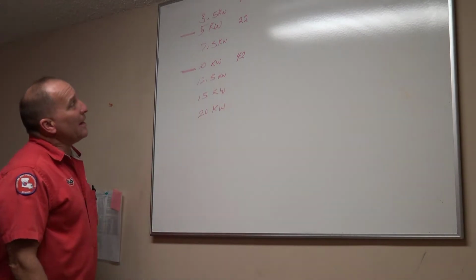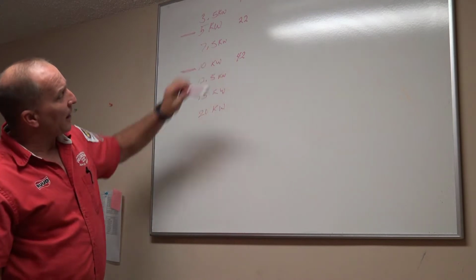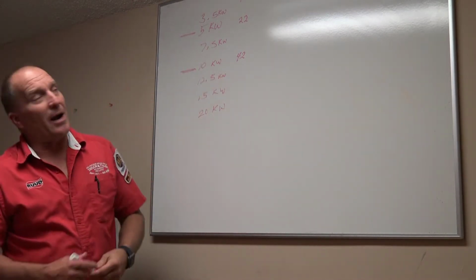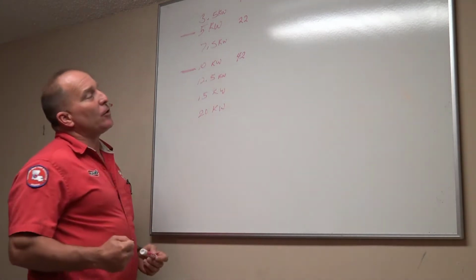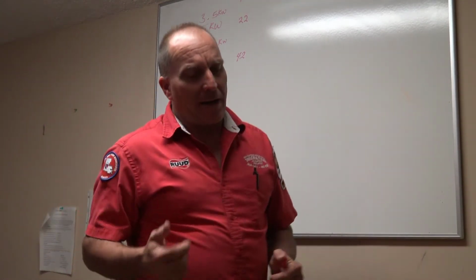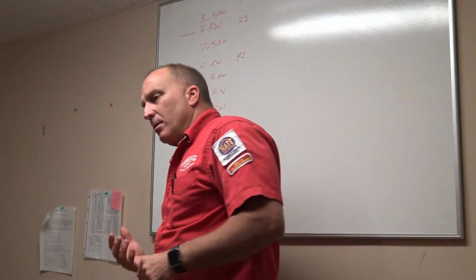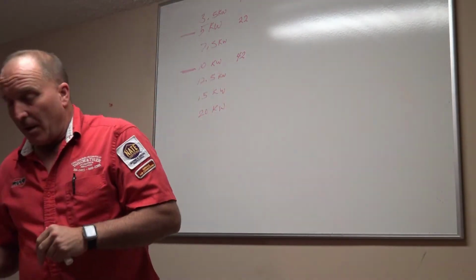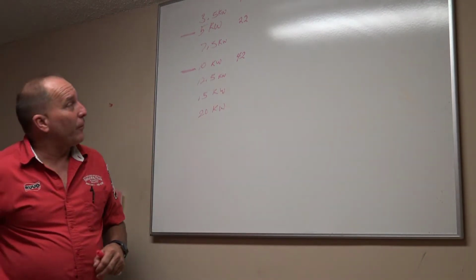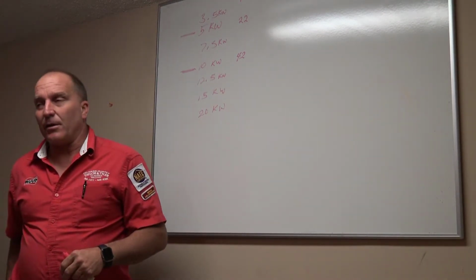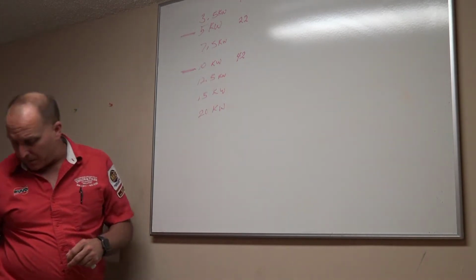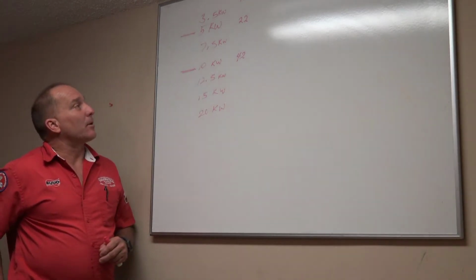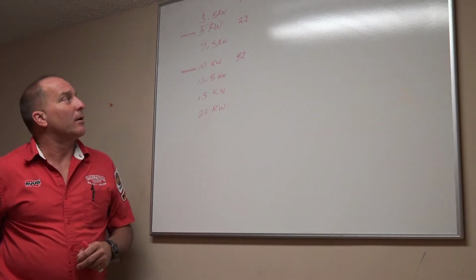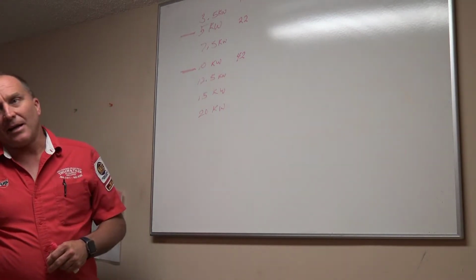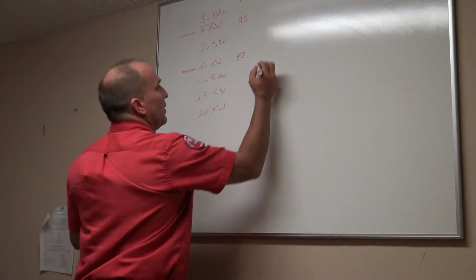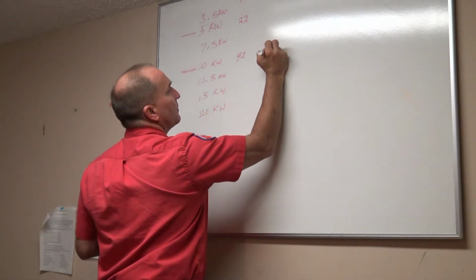Now I also need to know, if I'm drawing 42 amps, what breaker size do I need to hold 42 amps? Well, I can only apply 80% of the load of that system onto a breaker. So can I put a 40 amp breaker on there? No, it's drawing 42 amps, can't do that. Can I put a 50 amp? No, that's above 80% for sure. How about a 60 amp breaker? So let's go ahead and put a 60 amp breaker on a 10 kW system, and that 10 kW system is going to draw 42 amps. So we're going to go 60 amp breaker.